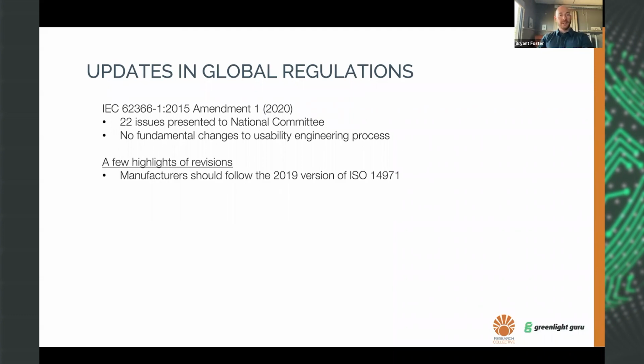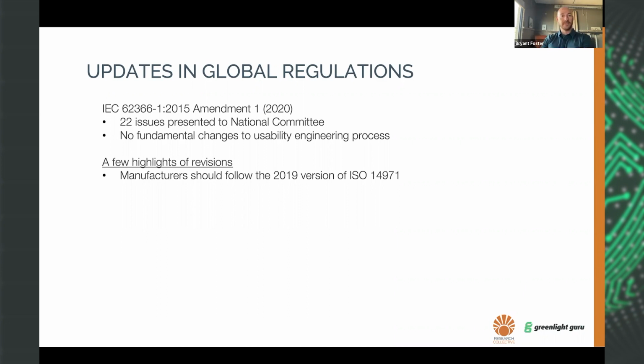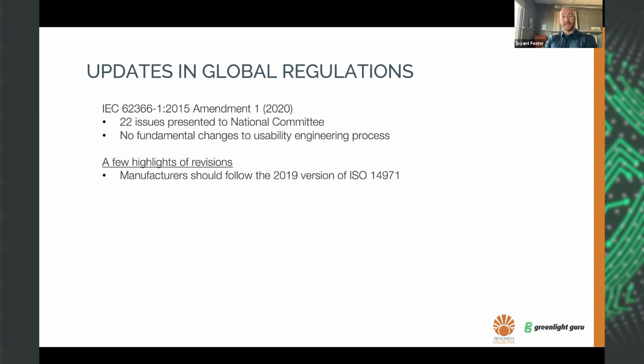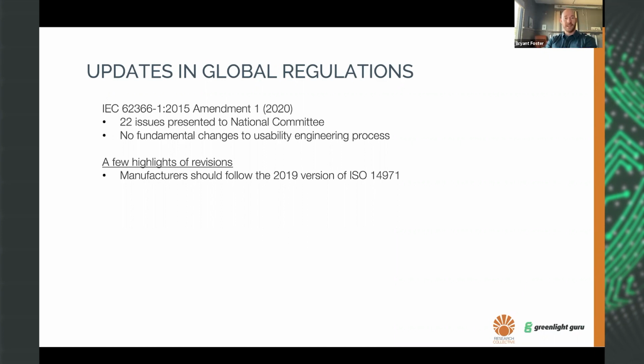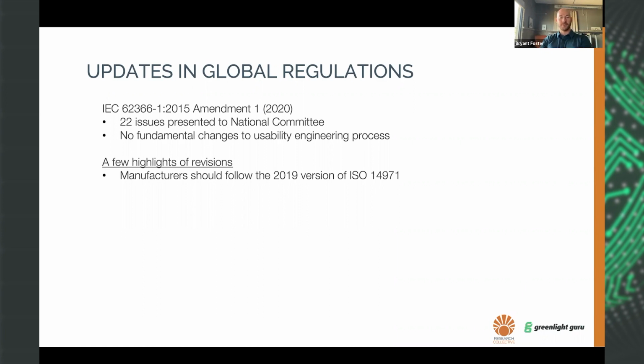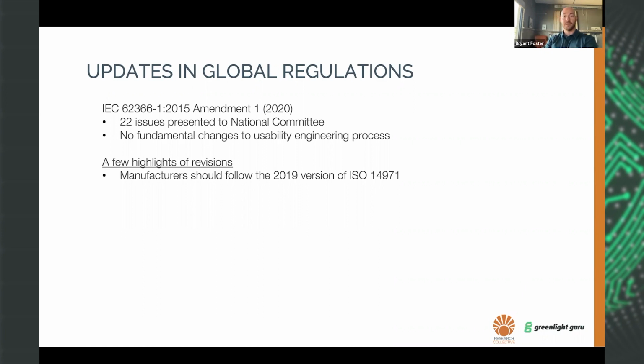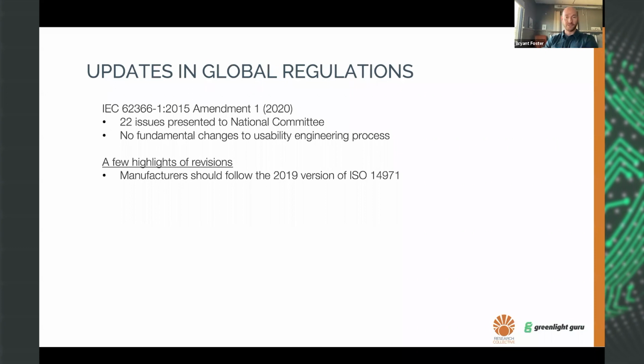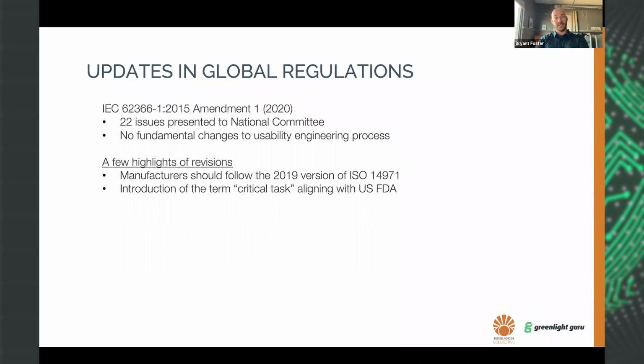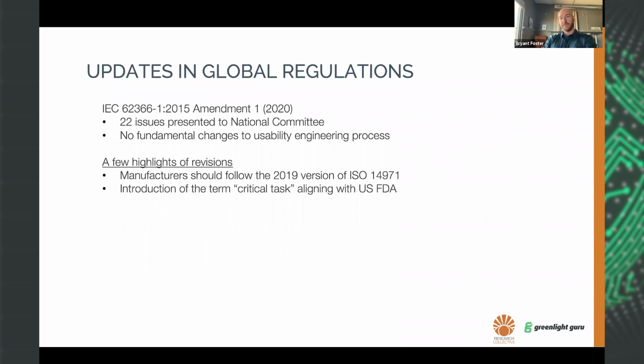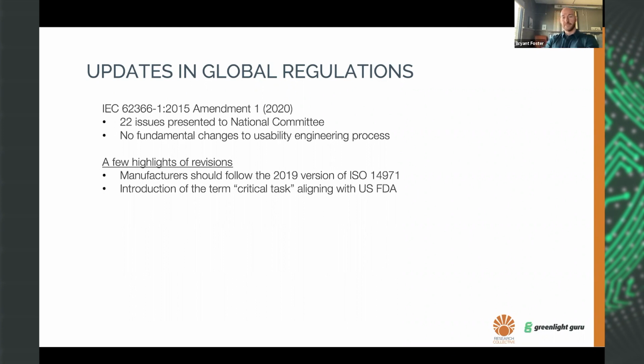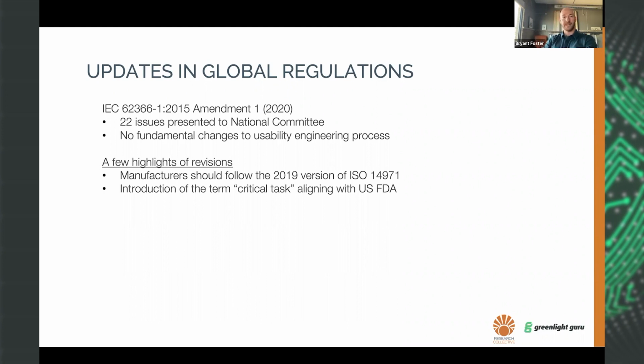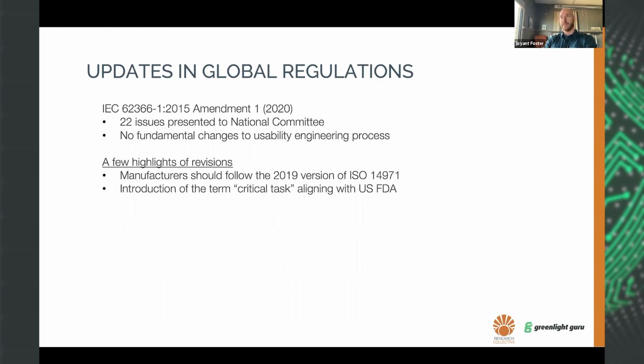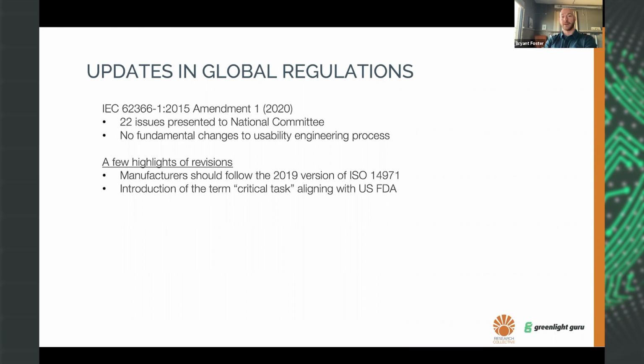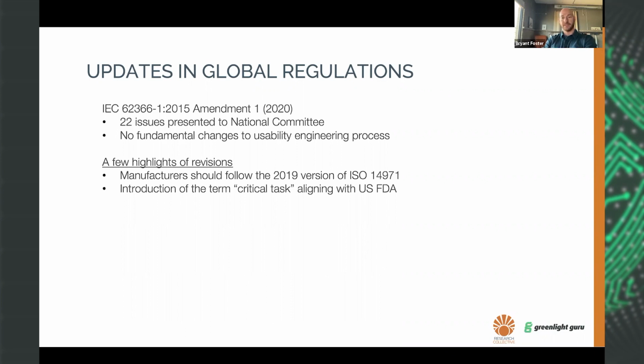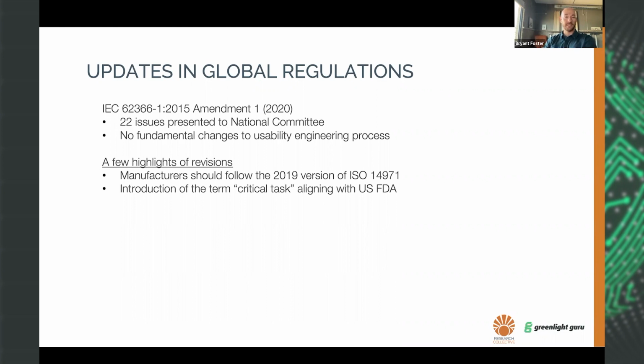So one clarification is that manufacturers, well, in 2015 there was no ISO 14971, which was released in 2019. And so now in 2020, they said, hey, make sure that you're following the ISO standard 14971 version 2019. Pretty straightforward. As I mentioned before, the introduction of the term critical task, aligning with FDA. And I think this came from, like I said, a lot of practitioners who said this method of identifying tasks that we're calling critical is a really nice way of defining what matters for the usability testing, and maybe those things that can be left or don't matter as much.